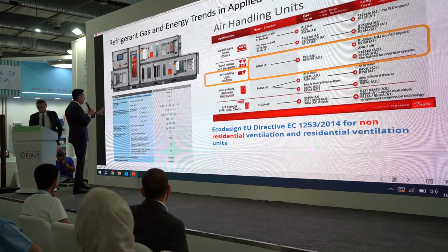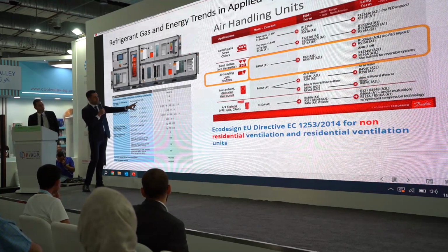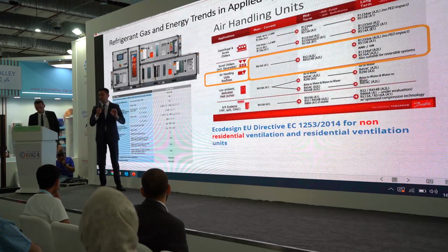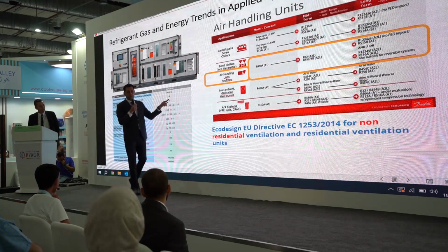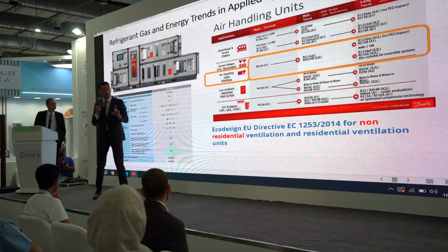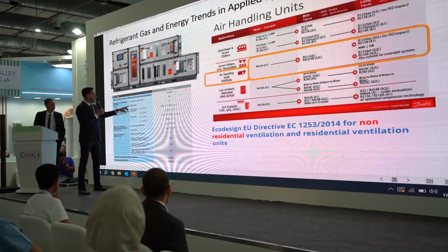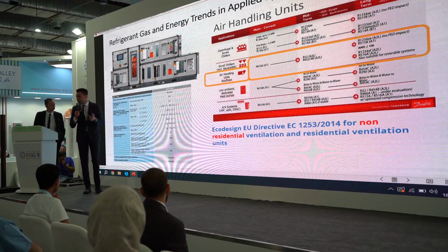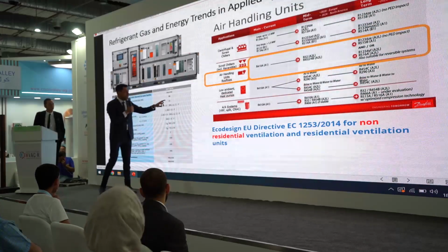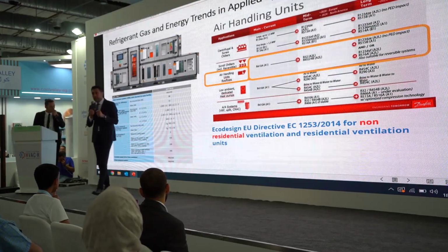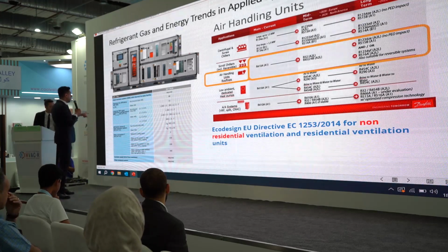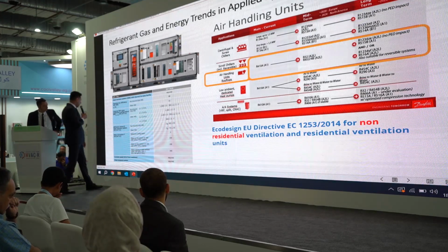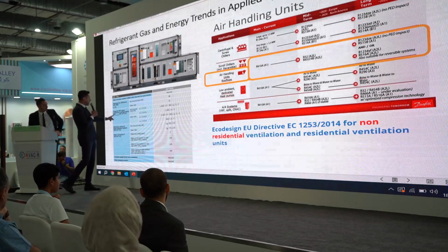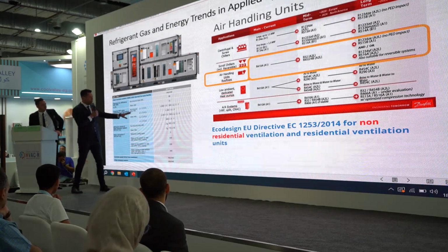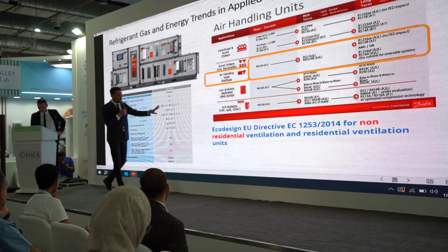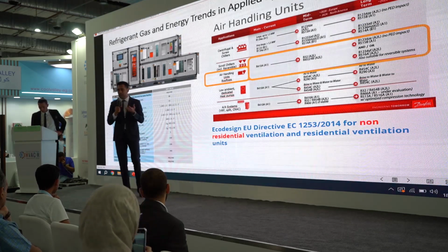For example, there's new legislation that for run-around coils, the minimum efficiency has to be 68%. Today maybe nobody is checking that here, I don't know. But for other kinds of heat recovery systems - plate, rotary wheel - it's going to be minimum 73%. You have to be certified too. There's also specific fan power level, SFP - depending on velocity, there must be limitations to increase system energy efficiency.